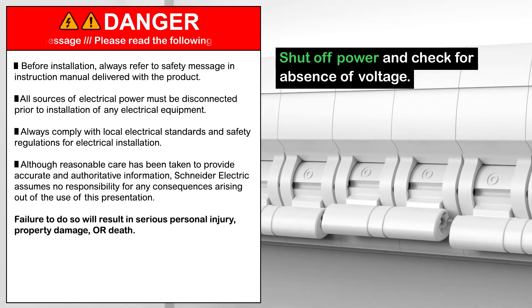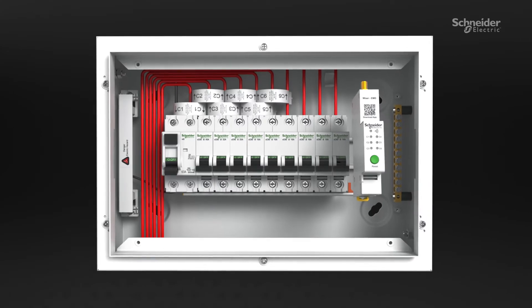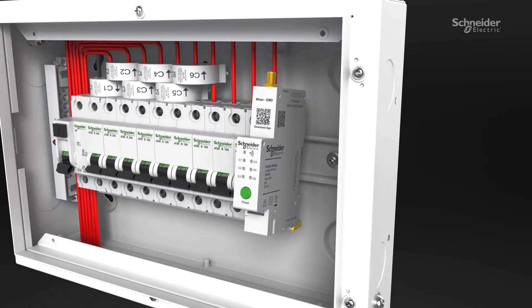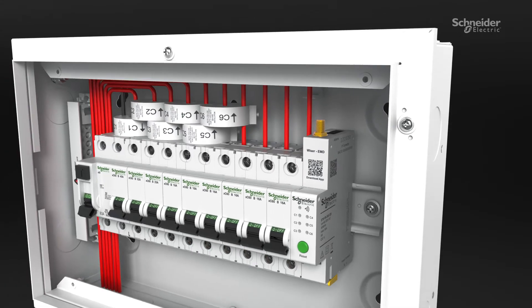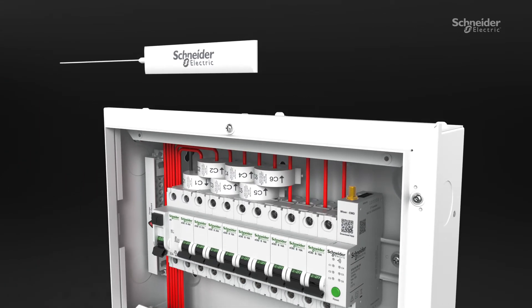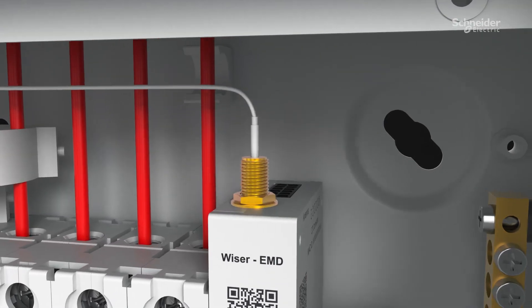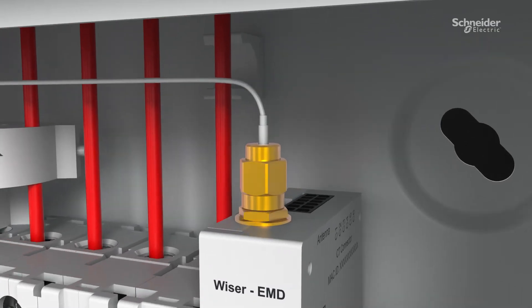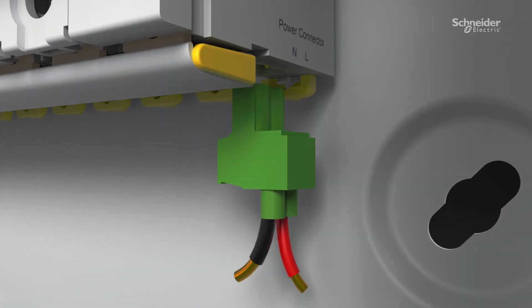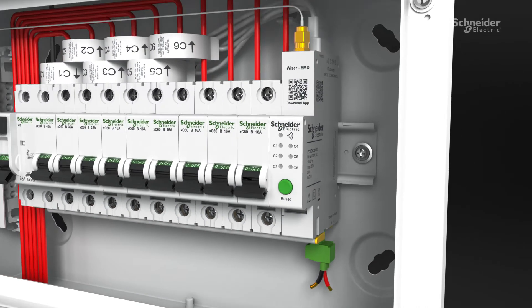Before you begin installation, turn off the power and ensure absence of voltage. Mount the device firmly on the DIN rails. Connect the patch antenna in its terminal, then connect the CT based on CT polarity direction on incomer and loads to be measured.